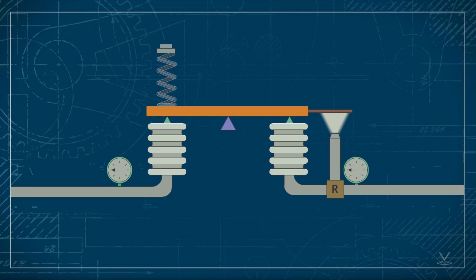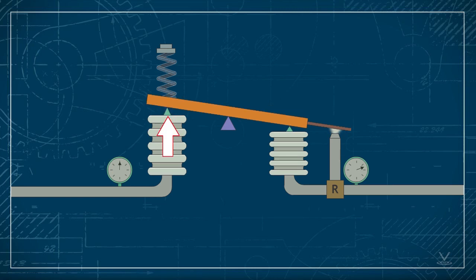If the process variable exceeds setpoint, the controller's input increases, expanding the input bellows. This increases the force of the input bellows and overcomes the spring tension. The beam moves up, causing the controller to be out of balance.